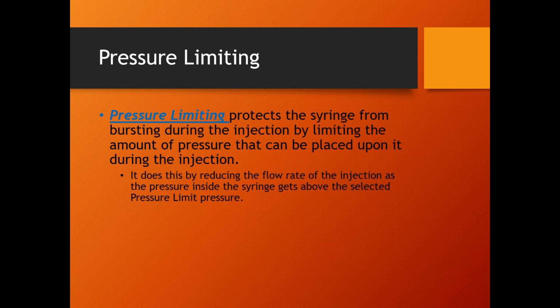If it doesn't, then we just have to shoot the patient again, figure out what the issue is and shoot the patient again. But if the injector stops, yeah, we're definitely gonna have to do it over again. So that's why for contrast injectors, if the system does hit its maximum pressure limit, it doesn't stop the injection, it just backs off on the flow rate. And then they'll assess if they need to reshoot again afterwards.